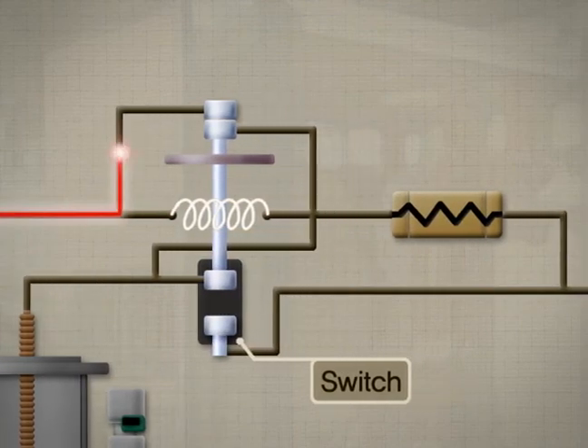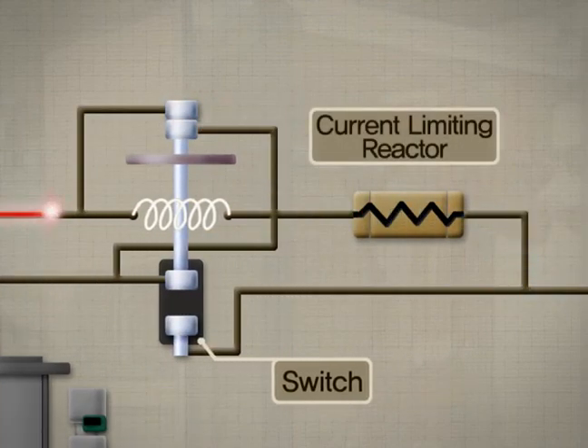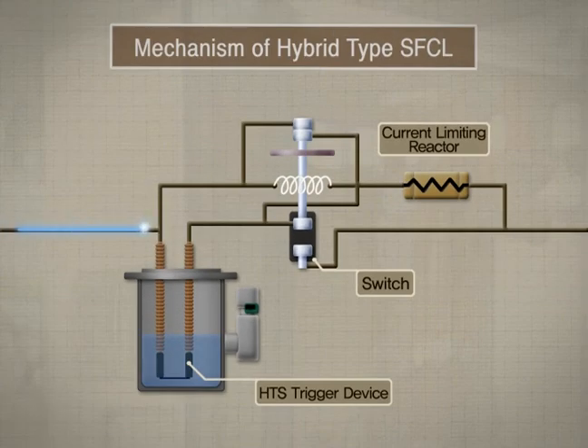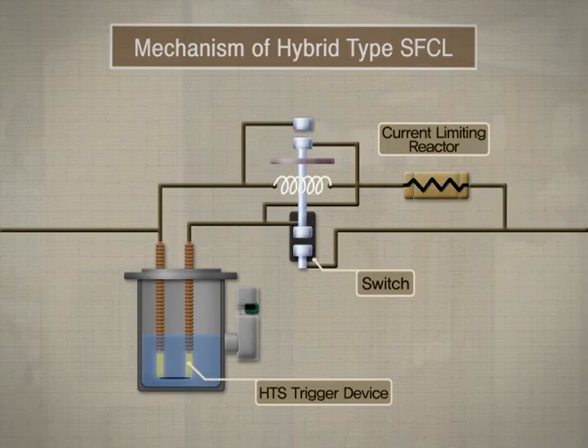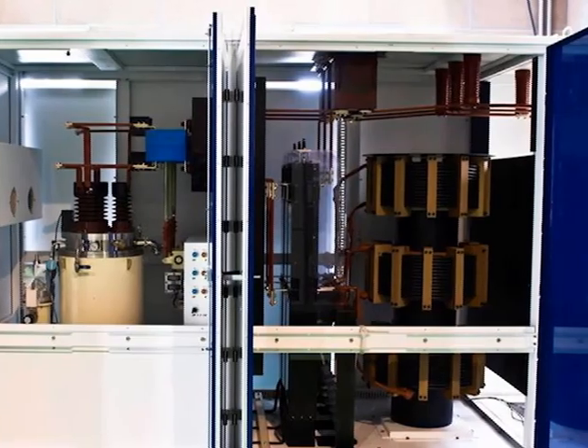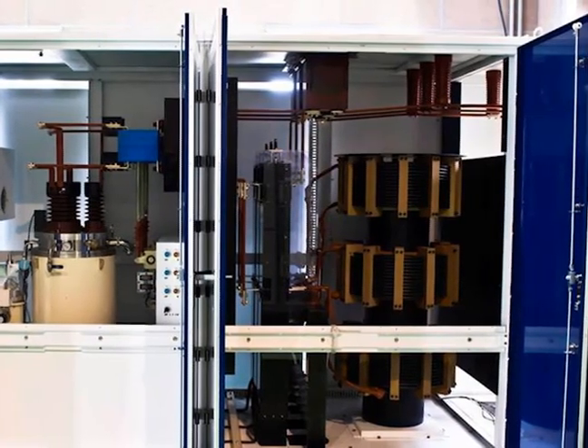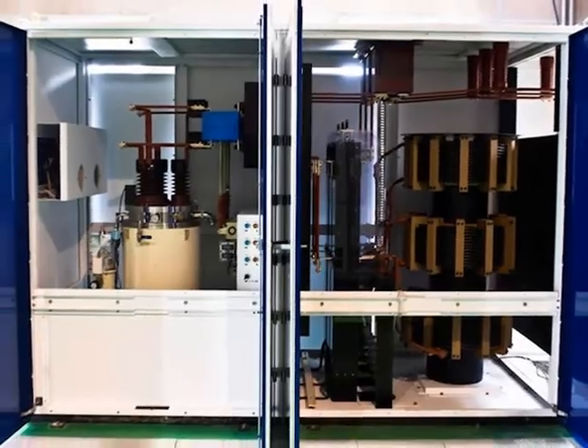This immediately forces the fault current to flow through the current limiting reactor that limits the current to a desired level. Since there is no current in the main path, the HTS module recovers its superconducting property shortly and gets ready for the next event. Therefore, the superconducting fault current limiter reduces the fault current of the power system immediately.